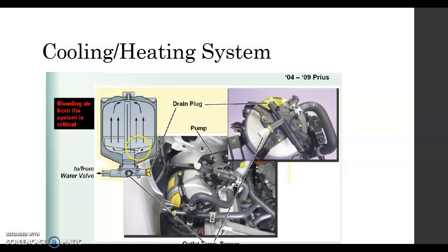It fills up this thermos with hot coolant, then pulls the hot coolant out from this spout tube, much like a hot water tank in your house with its downspout. As hot rises, the hottest water is up top, and that comes down this spout tube and back out to the valve—to and from, we'll talk about that in a second. That's how it fills up as well, keeping the cooler coolant on the bottom and the hotter on top.